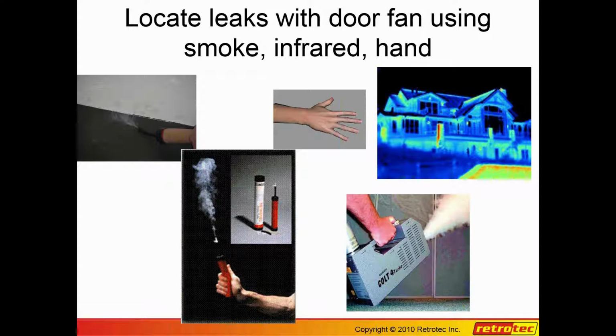What we would typically do, and to sensitize the hand, I like to use a little bit of rubbing alcohol, or vodka will work as well, but you might have a better use for that. Water if you don't have anything else. It really improves the sensitivity of the hand to airflow, done from the inside, of course, and done on a negative pressure of -25 if you can get it.